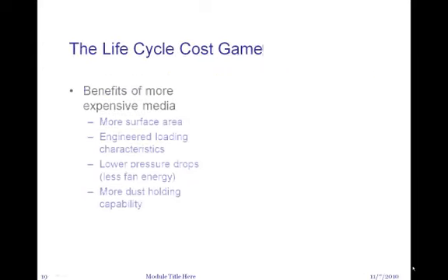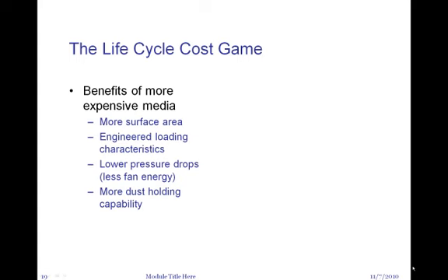Monitor those things. There are some advantages when you look at it that way to the more expensive filter media. You'll notice there's a big price variation between those filter types I have as samples. The more expensive media tends to give you more surface area and engineered loading characteristics where, as the filter loads, the pressure drop versus flow characteristic tends to stay very flat. Low pressure drop translates into fan energy savings. And the increased surface area means it can hold more dust, which is essentially what you're trying to do — capture and retain dust. So if the filter has more surface area to do that, that's a good thing.